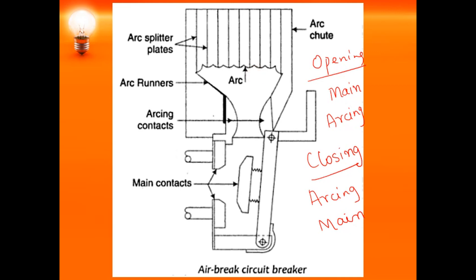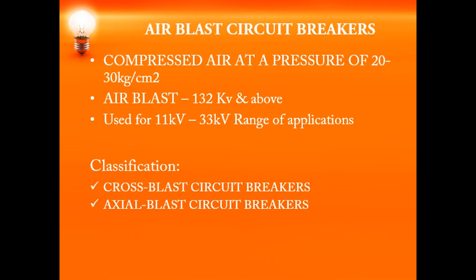Next we will see air blast circuit breakers. In air blast circuit breakers, compressed air is used instead of atmospheric pressure air. We use compressed air at a pressure of 20 to 30 kg per centimeter square. These air blast circuit breakers are suitable for operating voltages of 132 kV and above, and can also be used for 11 kV to 33 kV range applications. Air blast circuit breakers are mainly of two types: cross blast and axial blast circuit breakers.